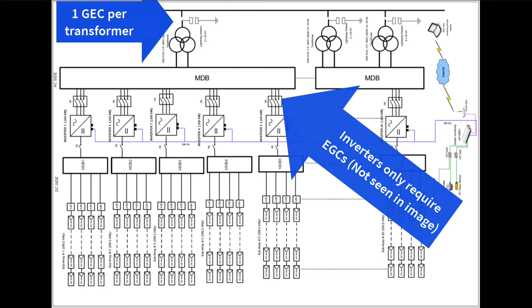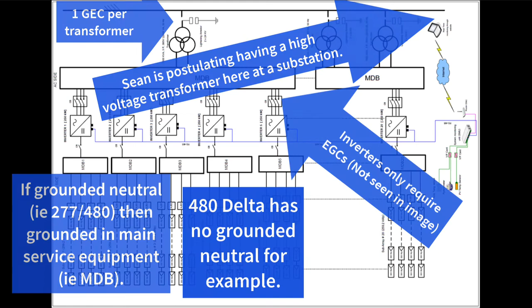And if they have a grounded neutral, which most inverters have, then that neutral will be grounded in the main service equipment. So like on a big power plant too, you might do this like 5-10 times or something, where you have multiple medium voltage transformers. Right. For each transformer you have a GEC. Yeah, each transformer would have a GEC at the transformer pad. And in this case, there might be an inverter pad that has all the inverters and a transformer on it. And then also where you combine all those transformers, a bigger transformer to go to high voltage. There may be, or it could just be a switch gear.